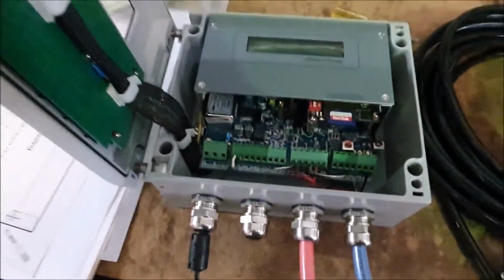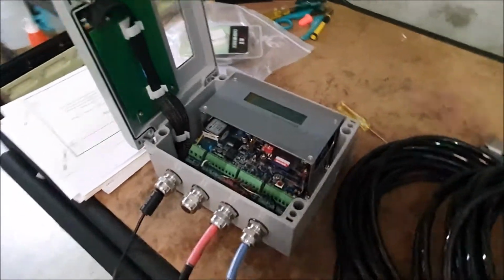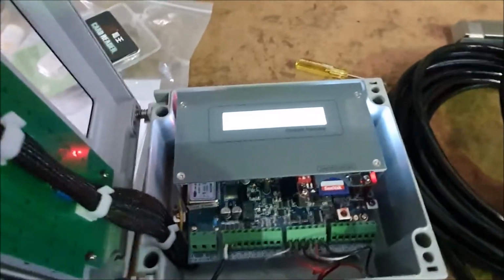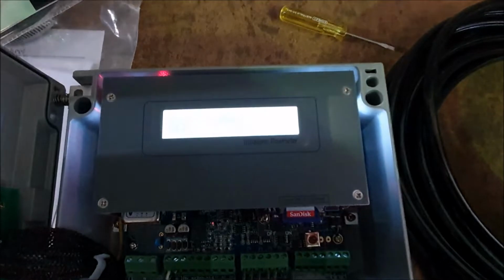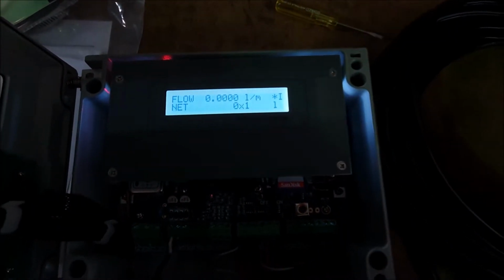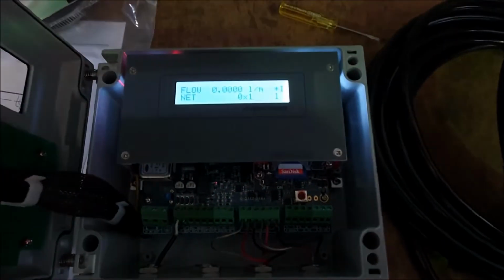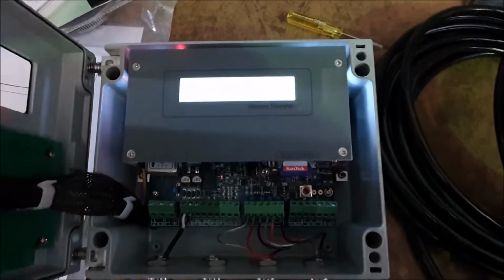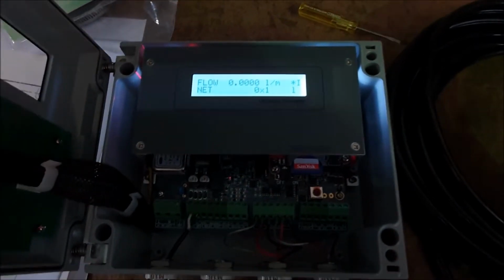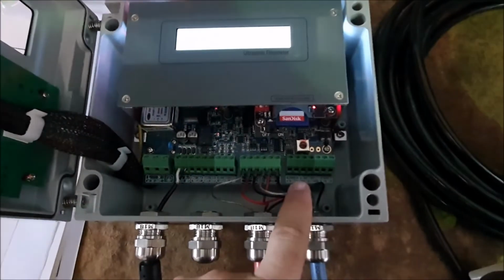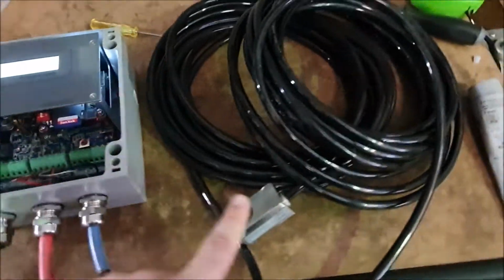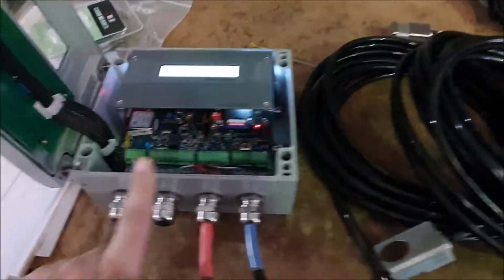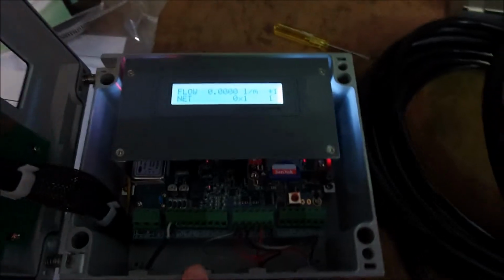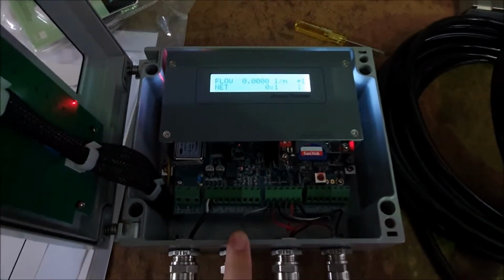We can quote a DC power supply if you need one. Okay, now I'm just going to turn on the power. And the flow meter will turn on. Okay, it's going to be hard to get the contrast ratio right on my camera. It is a nice, bright and easy to see screen in person. It's just hard to get right on the camera. Okay, so now that you've got the flow meter on, we've got our transducers connected. Okay, we do have to put the transducer still in the pipe, but first let's go through and set the parameters of the flow meter to the pipe we're going to install it on.